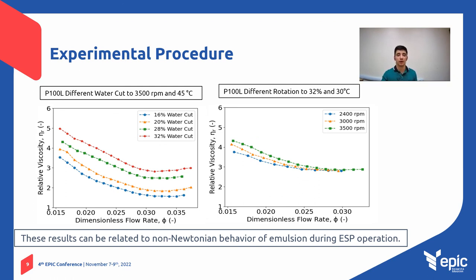Here, the influence of the dimensionless flow rate on the relative viscosity of the emulsion inside the ESP is shown. It is possible to notice that the relative viscosity increases as the dimensionless flow rate decreases for the analyzed water cuts. The ESP viscous performance degradation caused by emulsion can be intensified by effects such as shear-thinning behavior.